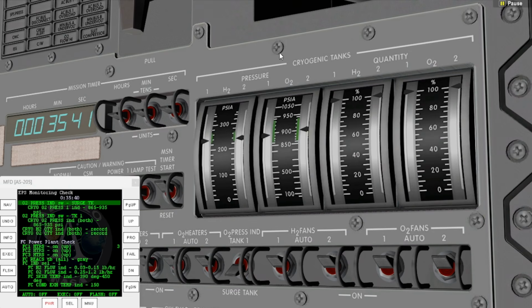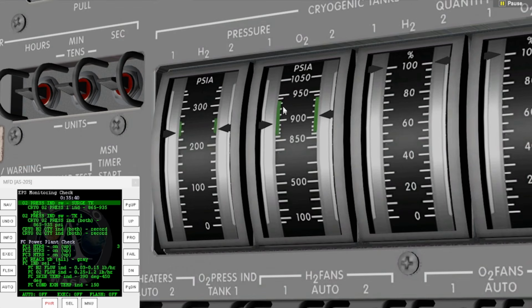Surge tank on the O2 pressure. So take a look at this. Cryogenic tanks, oxygen. 2 is a single function gauge, but 1 is a double function gauge. It can be switched between the surge tank and tank 1. So here, oxygen pressure indicator, tank 1, surge tank. We're on surge tank. That should be between 865 and 935. Again, wouldn't you know, nice green band.